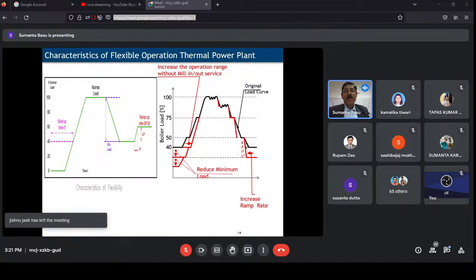Now, to address these situations and come out of them, because tomorrow we are going to have 62% non-fossil based generation, which does not have primary frequency response characteristics and generates only active power. So how, by controlling the active and reactive power, can we come out of these situations? How should the already existing generating systems, coal or gas fired, be operated more flexibly so that these disturbances can be mitigated?